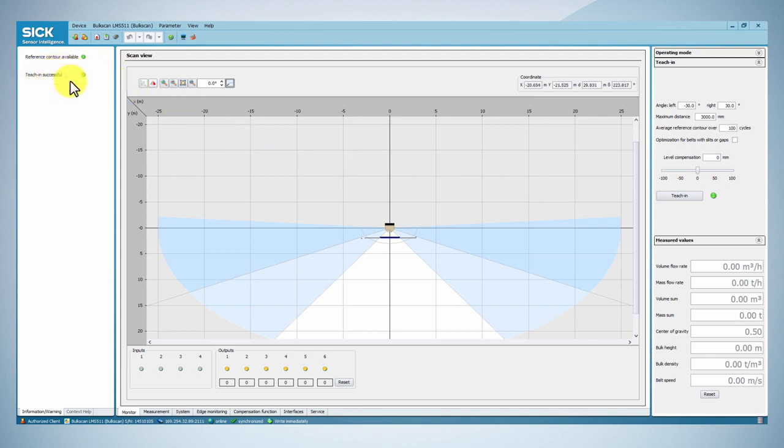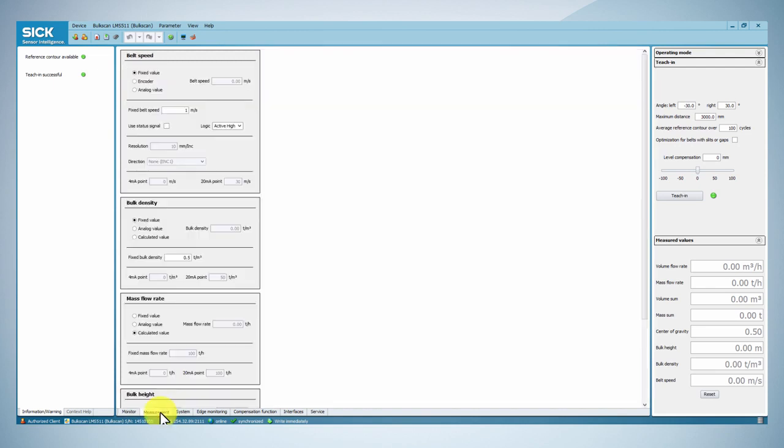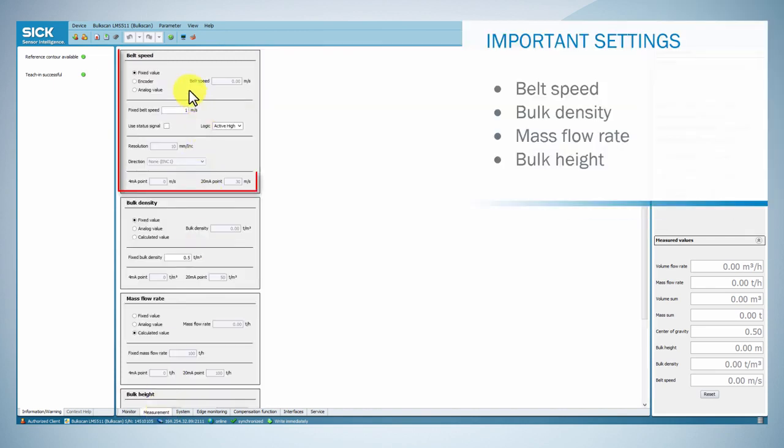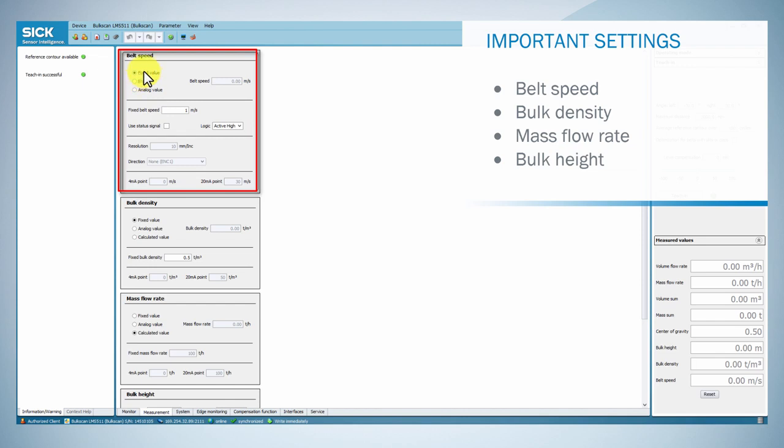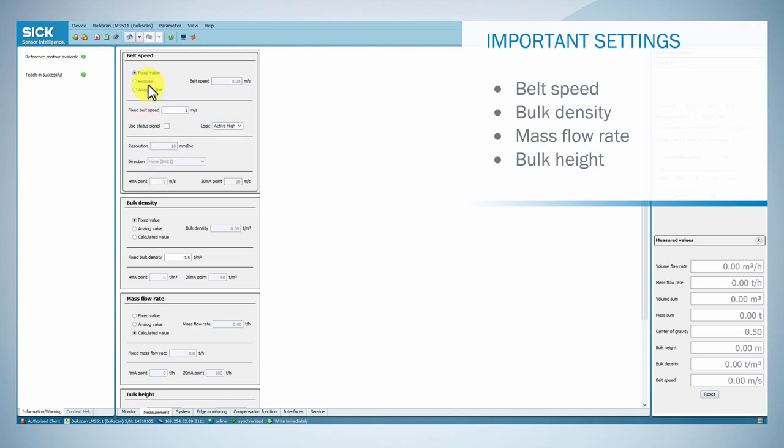In the measurement tab, you can select a source for the conveyor belt speed. It is possible to use a fixed belt speed value, to use an incremental encoder, or to input an analog current signal using the BAM100 analog module.